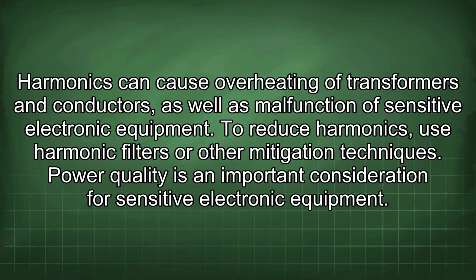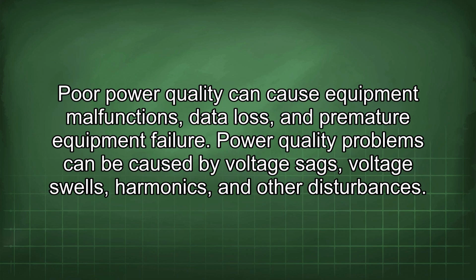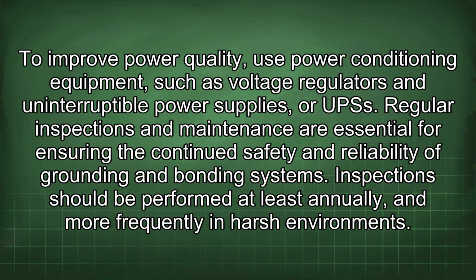Power quality is an important consideration for sensitive electronic equipment. Poor power quality can cause equipment malfunctions, data loss, and premature equipment failure. Power quality problems can be caused by voltage sags, voltage swells, harmonics, and other disturbances. To improve power quality, use power conditioning equipment such as voltage regulators and uninterruptible power supplies, or UPSs.